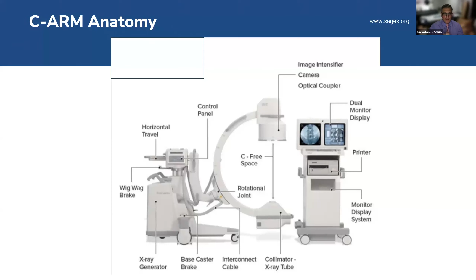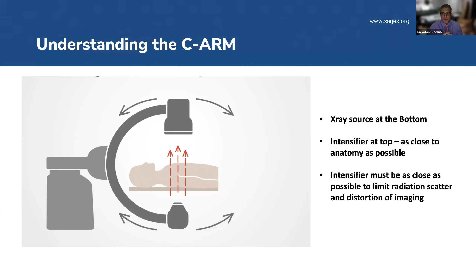So the C-arm can move in two different main directions. The X-ray source that I mentioned earlier is coming from the bottom, so it's going bottom to top. The intensifier, as I mentioned, is located at the top and captures all the X-rays. In order to get the best picture and to reduce radiation scatter, you really want to have the intensifier as close to the patient as possible. And that's the key. It's not the X-ray beam itself, but the intensifier that gives you the best pictures.